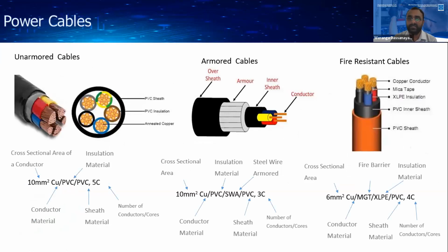When you are going for a power cable, there are several types of power cables available in the market. The first one is armored cable. Armored cables are basically used to distribute power underground or in open areas, because these armored cables are equipped with steel wire armor around the conductor. Sorry, here this one is an unarmored cable. An unarmored cable has no mechanical protection. Very sorry, this first one is an unarmored cable. That means there is no mechanical protection around this cable, just an insulation around the conductor and a PVC sheath surrounding all the conductors.